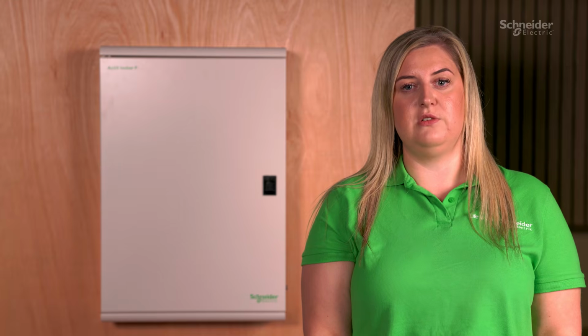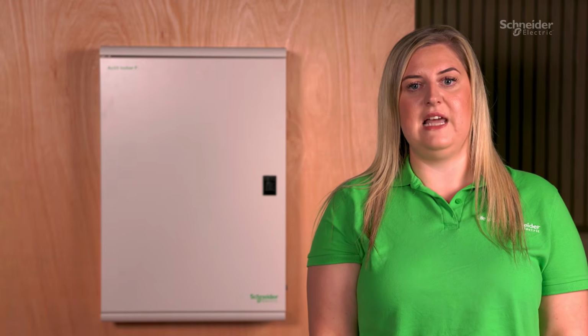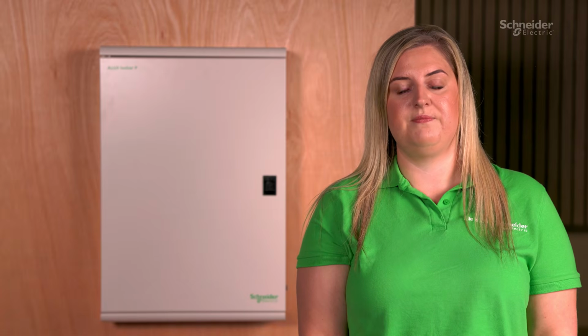One point to consider when fitting your new Type 2 and 3 SPD is to check it coordinates with any upstream surge protection device. This ensures that surge protection devices work together effectively to safely manage and dissipate electrical surges, protecting your equipment and maintaining system reliability. On our range page, you'll find our coordination schedule with the relevant Type 1 and 2 Schneider Electric devices, so you can guarantee coordination between all of your devices.